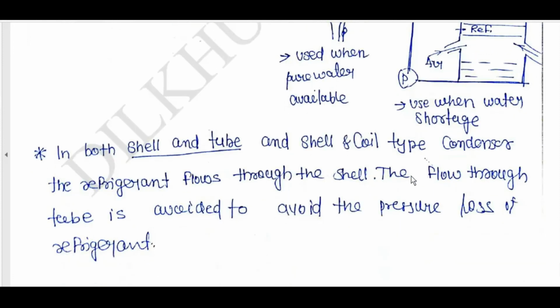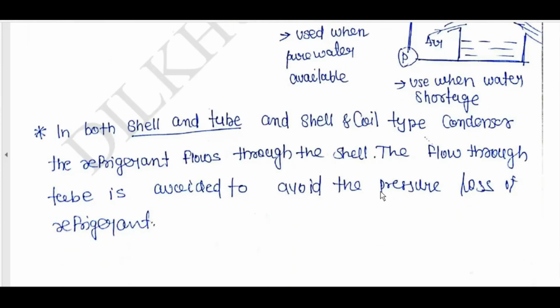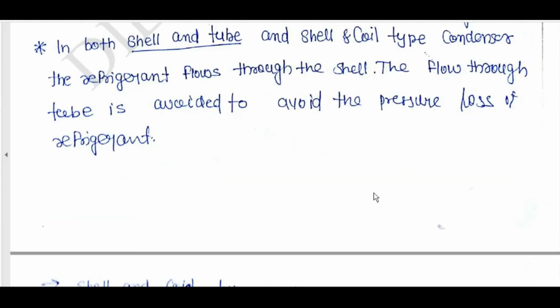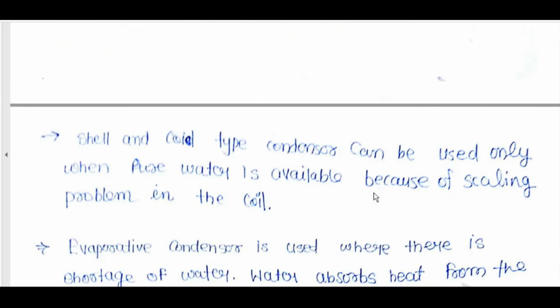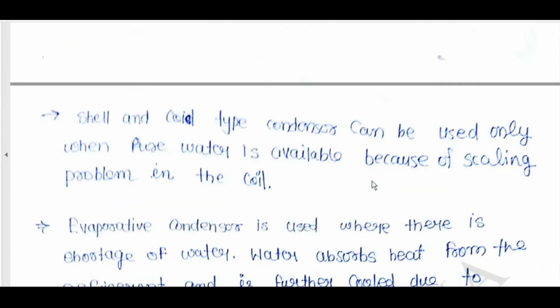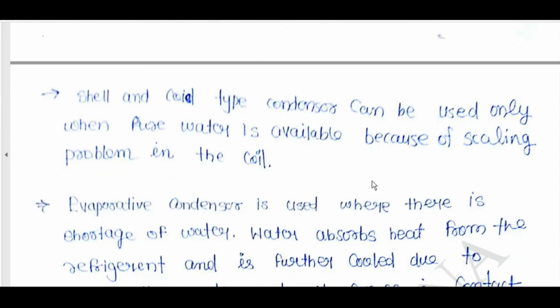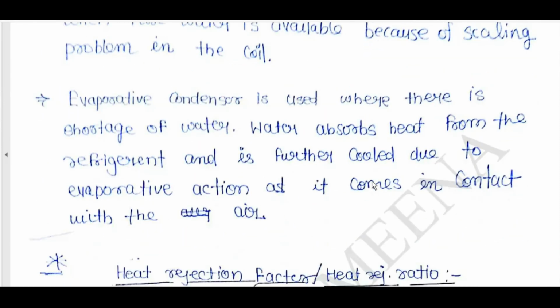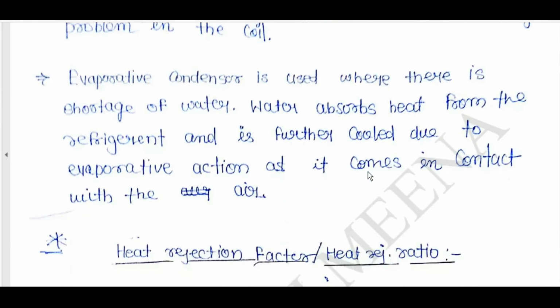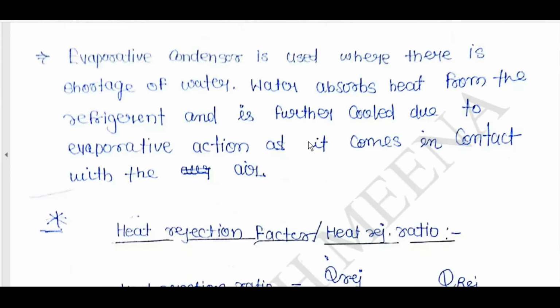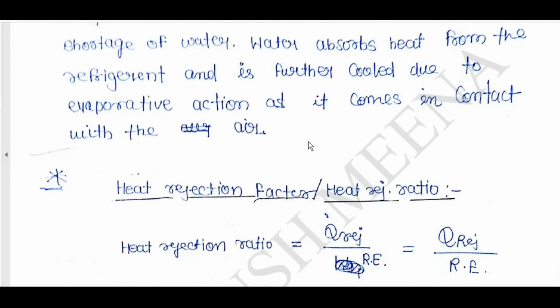The flow through the tube is avoided to avoid pressure loss of refrigerant. Shell and coil type condenser can be used only when pure water is available because of the scaling problem in the coil. Evaporative condenser is used where there is a shortage of water. Water absorbs heat from the refrigerant and is further cooled due to evaporative action as it comes in contact with air.